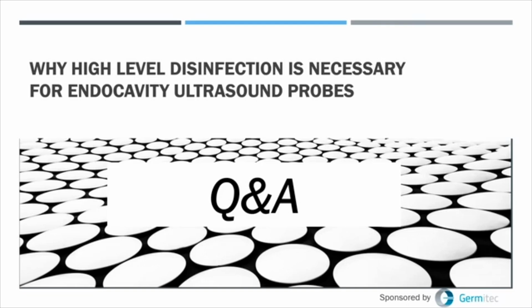Next question, do you have thoughts on the use of wipes for HLD? So the concerns about wipes for HLD as opposed to another method such as UVC are a number. I've already talked about redundancy. Here I'll also mention that to the extent possible in medicine, we've always found re-engineering a system is better than trying to educate individuals on how to do something properly. That's why when you look at, say, an automatic endoscope reprocessor for an ERCP scope that automatically cleans and disinfects an ERCP scope or duodenoscope, you find lower risks of contamination as opposed to having a human do all the manual cleaning and the manual chemical disinfection. If they did the cleaning and disinfection 100% of the time, it would work.